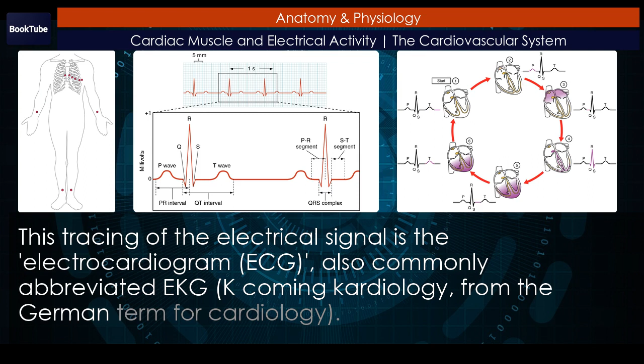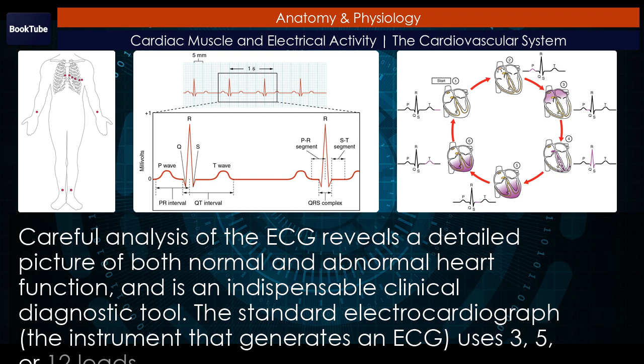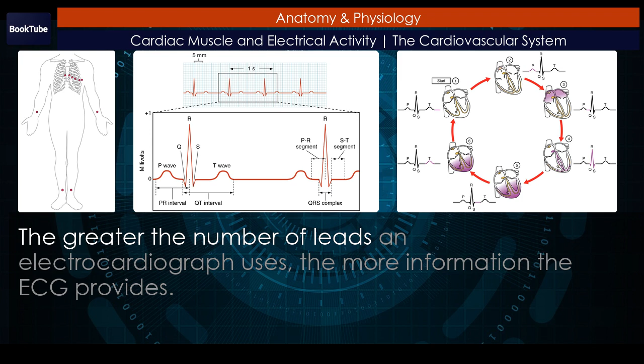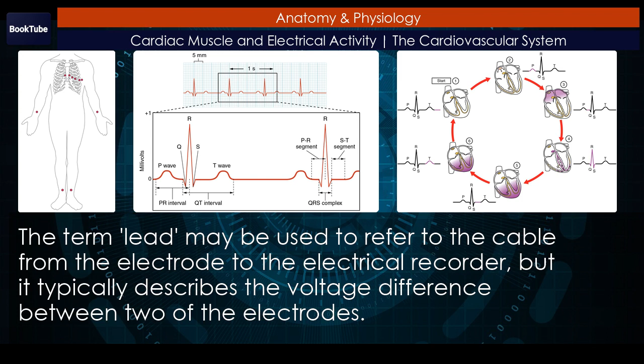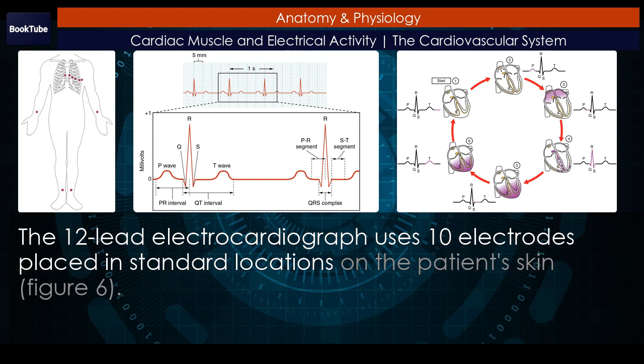The standard electrocardiograph, the instrument that generates an ECG, uses 3, 5, or 12 leads. The greater the number of leads an electrocardiograph uses, the more information the ECG provides. The term lead may be used to refer to the cable from the electrode to the electrical recorder, but it typically describes the voltage difference between two of the electrodes. The 12-lead electrocardiograph uses 10 electrodes placed in standard locations on the patient's skin.